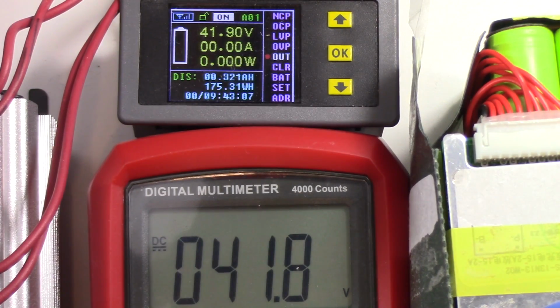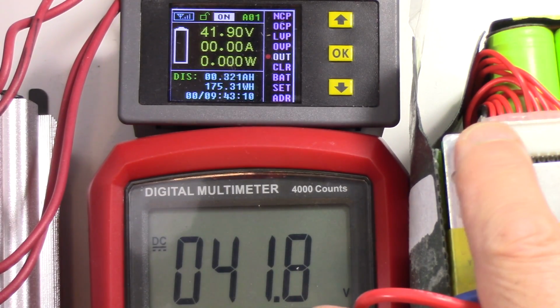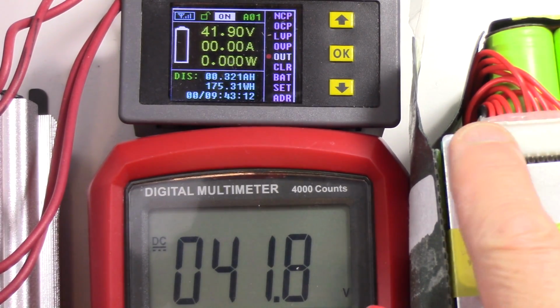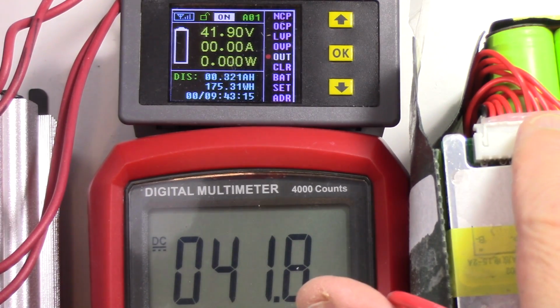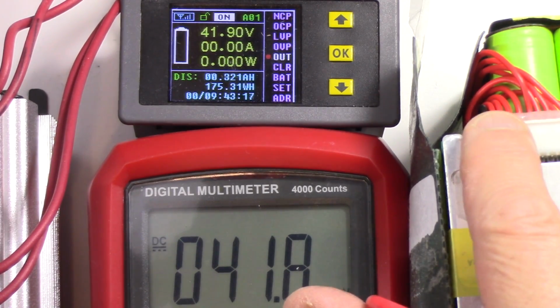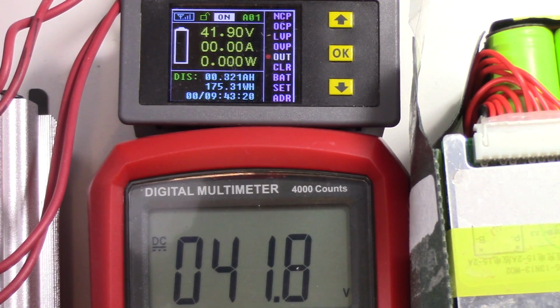Now I did get it up to 42 volts by individually disconnecting the BMS connector and the battery connector, and individually charging each cell to 4.2 volts, which brought the whole pack up to 42 volts - that's how I did the discharge capacity test. But knowing I can't charge it beyond 41.9 and can't discharge it to 27.5, that should change the entire capacity rating of the battery pack as far as what you'll get out of it using the BMS connected.